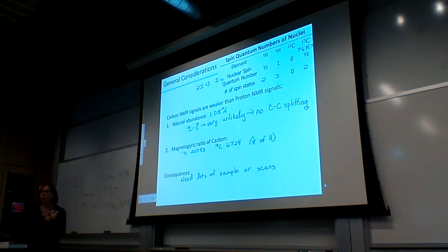So it's about 1/4. Is that why you have to tune the NMR to be like phosphorus or? That's part of it, yeah. It's set up automatically to do proton and carbon, but for any other nuclei that has a different magnetogyric ratio, we would have to tune it to the right frequency so that you can get those transitions.